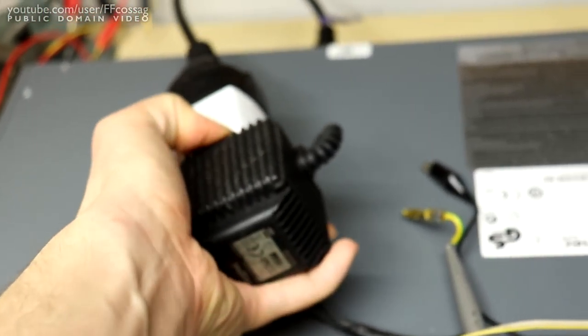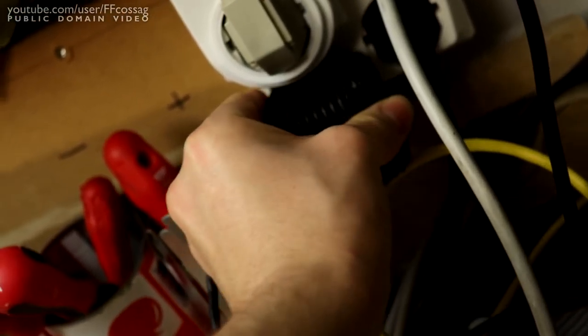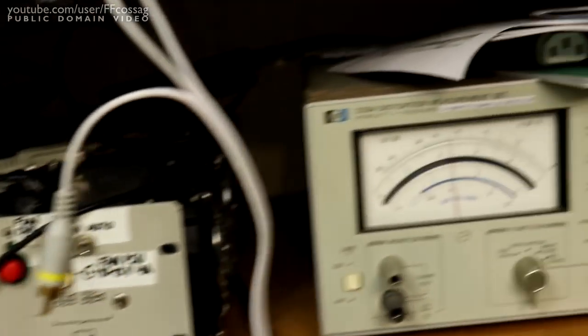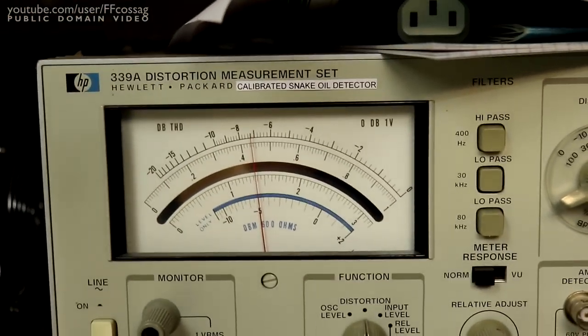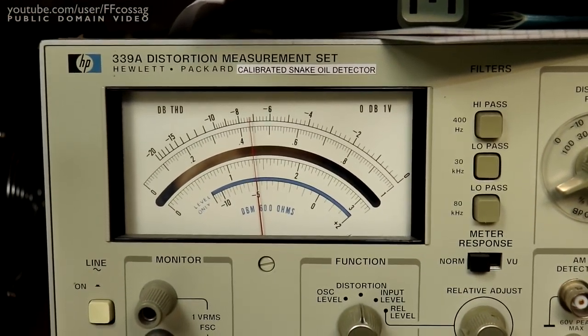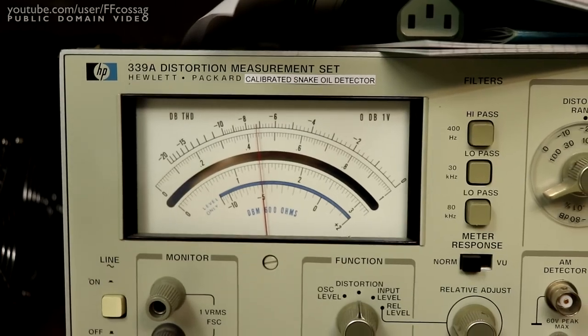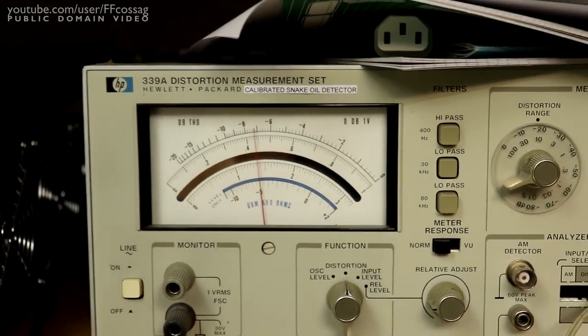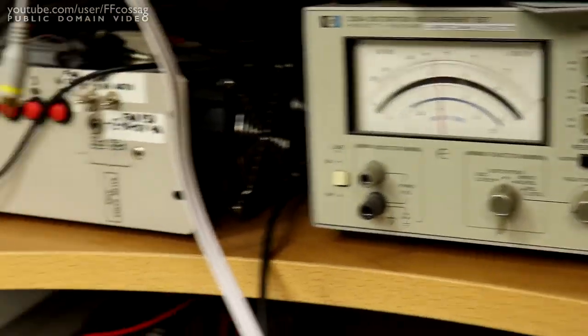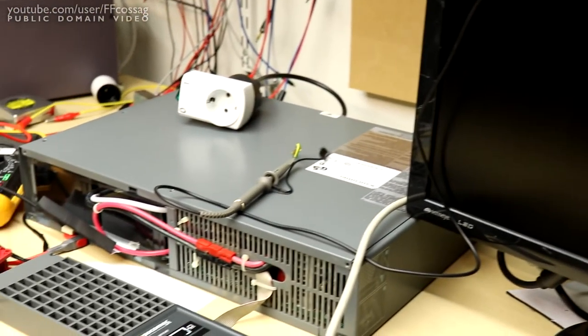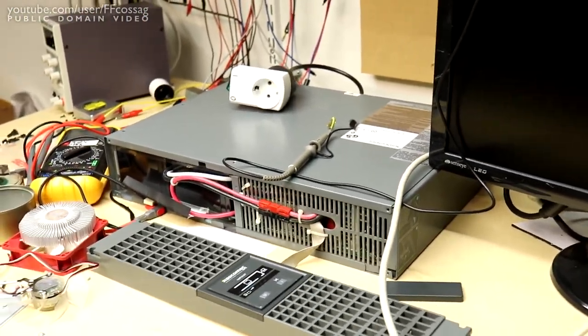Grab the transformer and shove that back into the wall, and we are straight back to well over 4% of distortion. So the UPS certainly is doing its job in actually cleaning the power up.